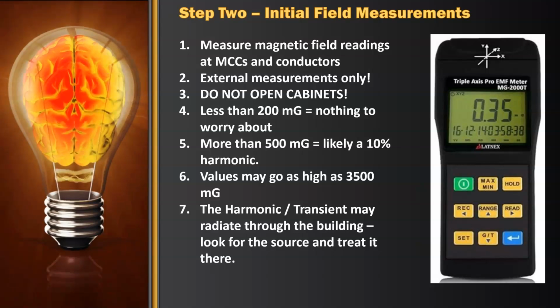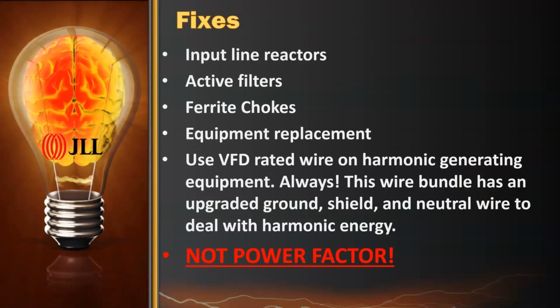And now we're going to talk a little bit about fixes. Let's make sure I get the slide in the right order here. Fixes. Perfect. There are lots of different ways to treat a harmonic. One is a passive way, an input line reactor, which is basically a specific type of transformer, only half of the transformer. It's got a lot of wire in the winding, and the whole thing is designed for that stronger magnetic field to get a crimp put in it and basically slow it down.